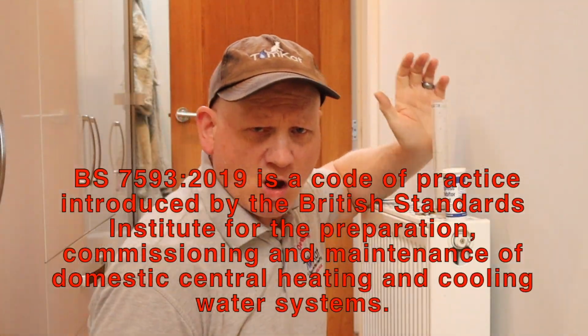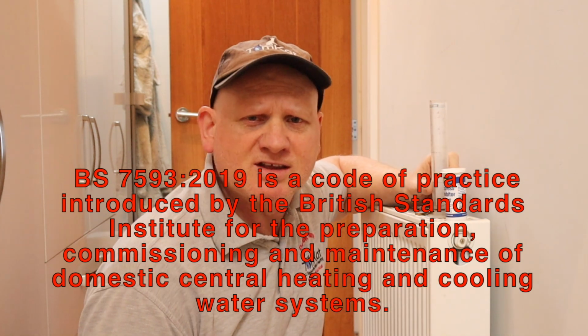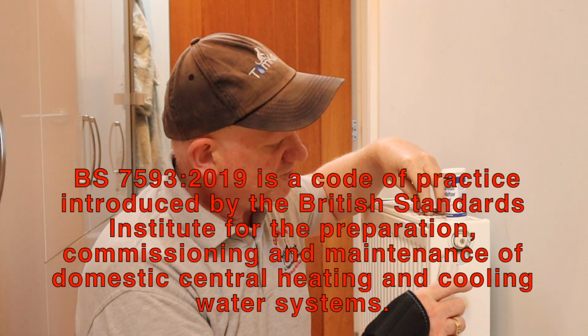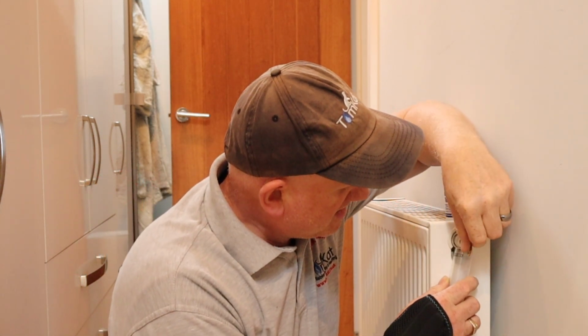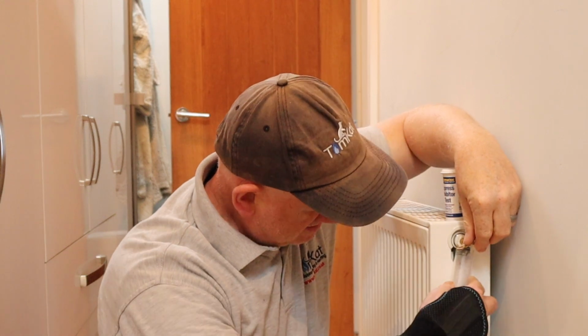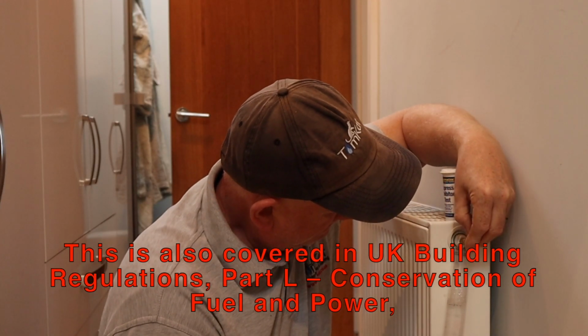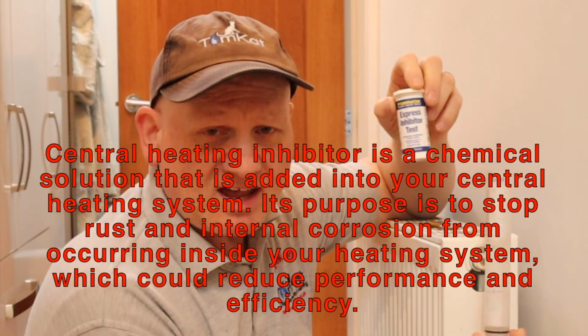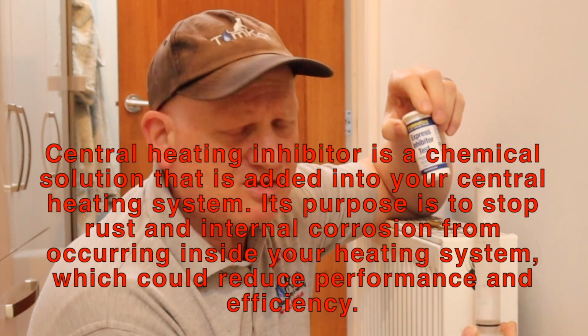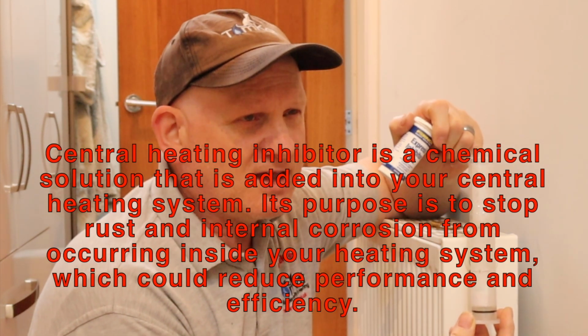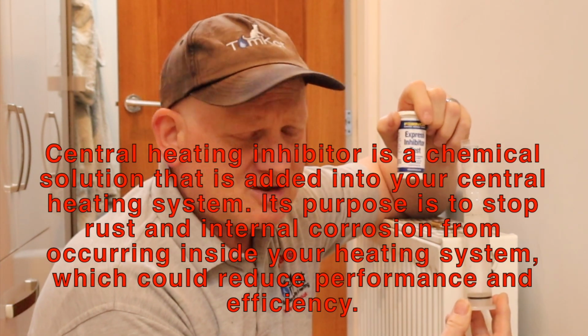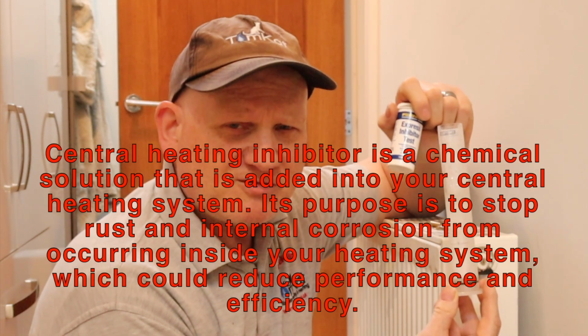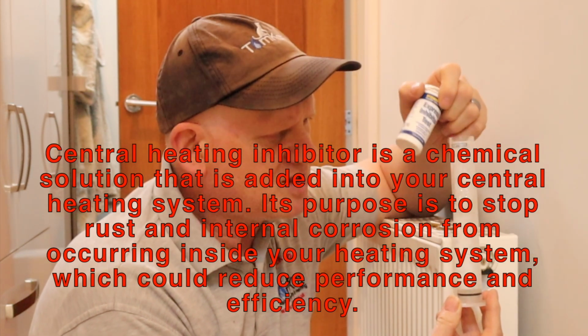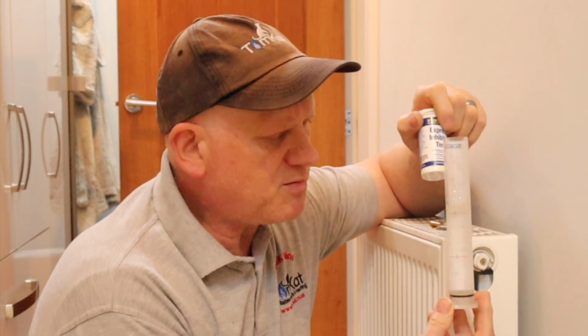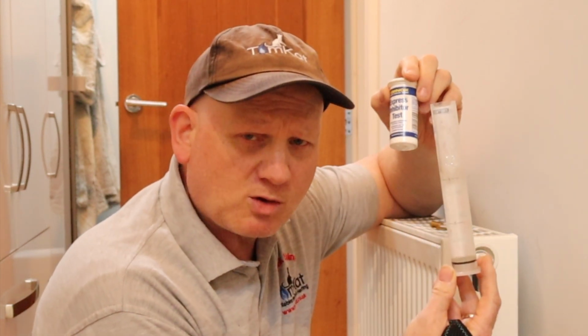Another important test, which always seems to get missed on services, is checking the water quality. So first, taking a sample out of a radiator using your turbidity tube, and then using your test strips to see if there is actually any inhibitor in the water. Now what this is going to do is tell you whether the system needs flushing and cleaning, or whether any faults that have occurred are because of dirty system water. So always make sure on a service or repair that you actually test what the water quality is and if there actually is any inhibitor in there.